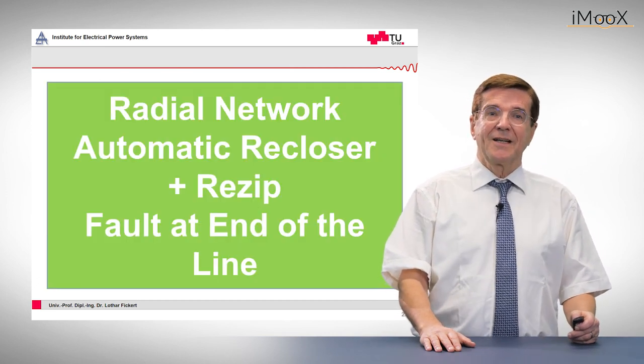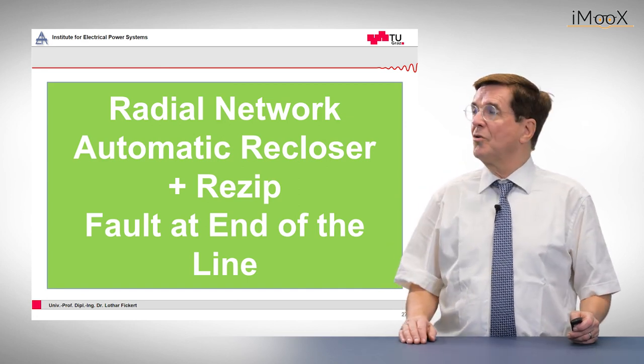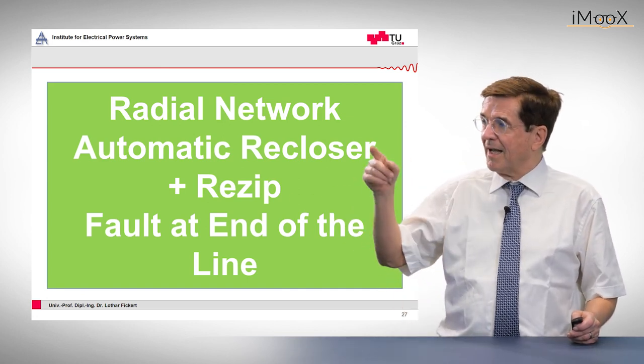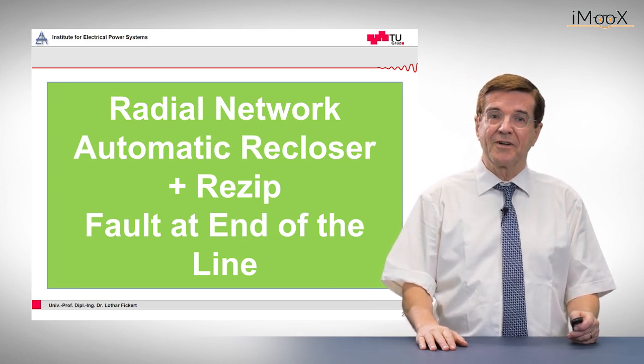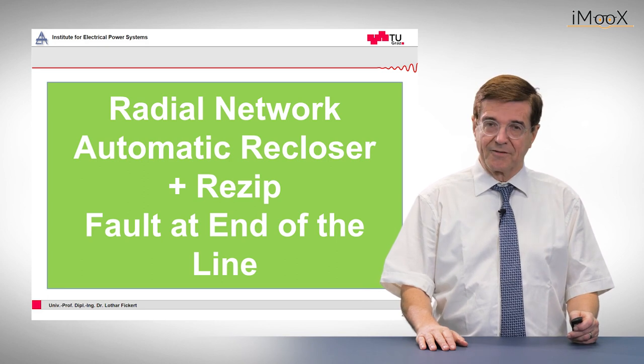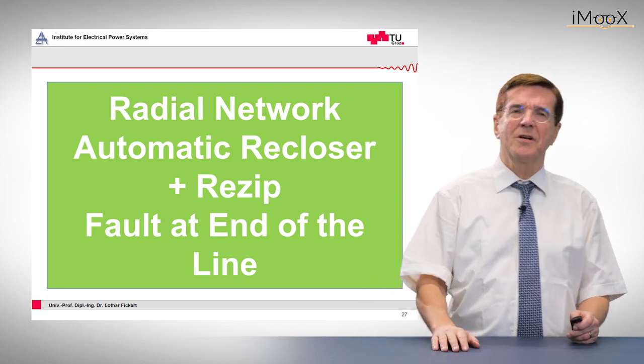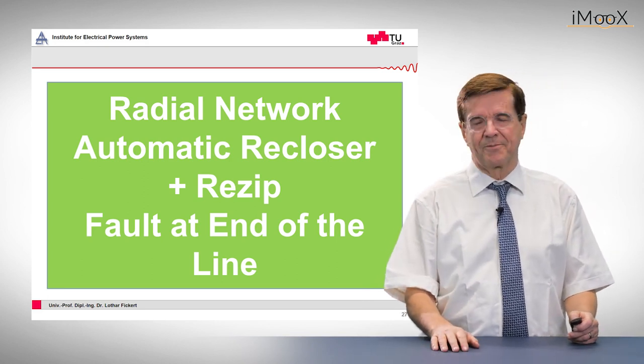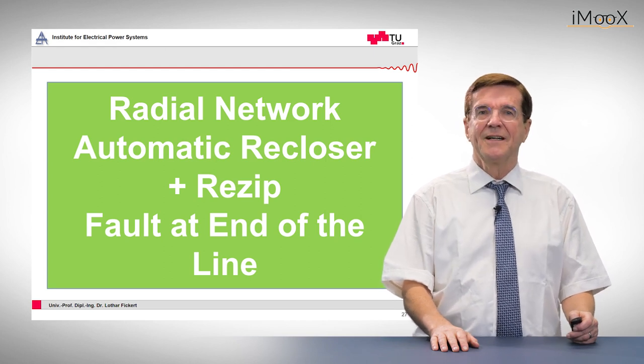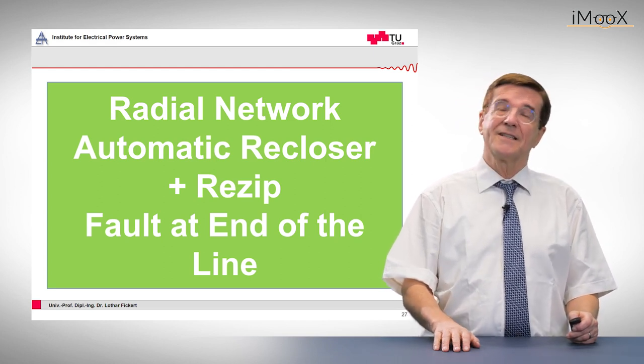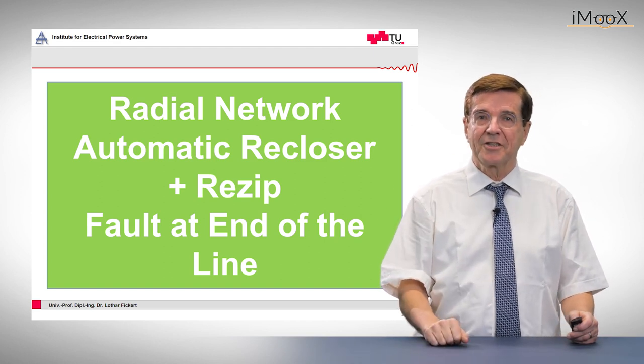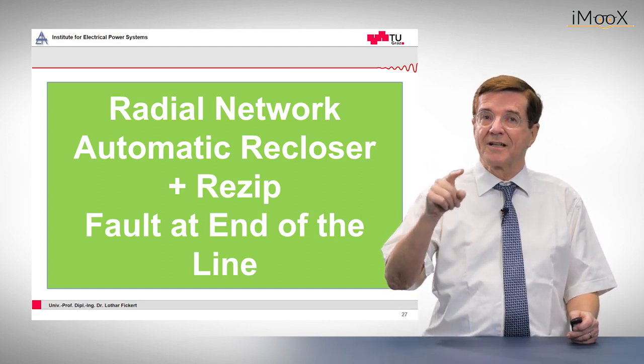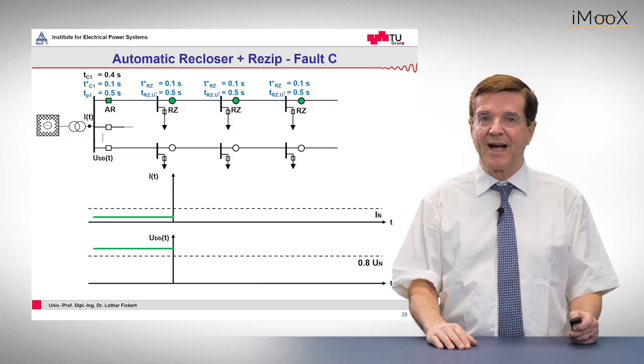Now let's look at a radial network with an automatic recloser and a re-zip recloser. This is a new type of protection device and a fault at the end of the line. Let me give you a few words about this principle of the re-zip recloser. A re-zip recloser is a device that is not only capable of time graded protection but also of logically graded protection. And we see how it works.